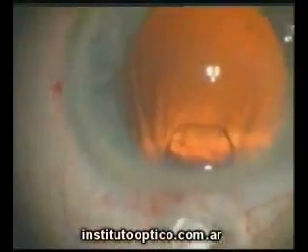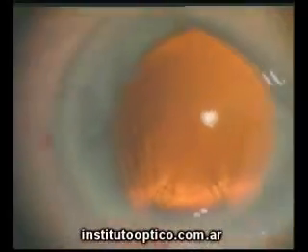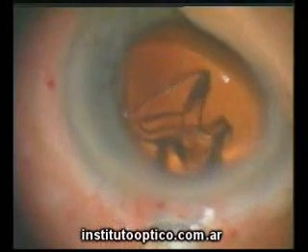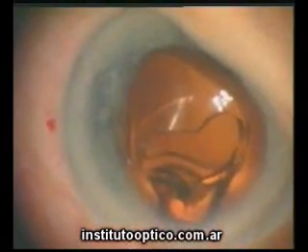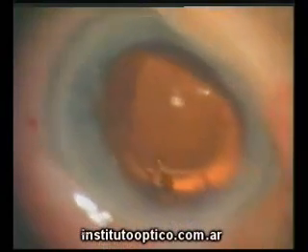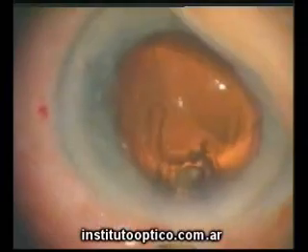The Rayner injector can be used with a 3mm to 3.6mm incision, depending on technique. With the Rayner injection system, the lens can be injected straight into the capsular bag. As the lens emerges from the injector tip, the leading haptic gently unfurls into the bag, followed by the optic body and trailing haptic, which can be easily placed with the tip of the spring-loaded plunger over the capsulorhexis rim.